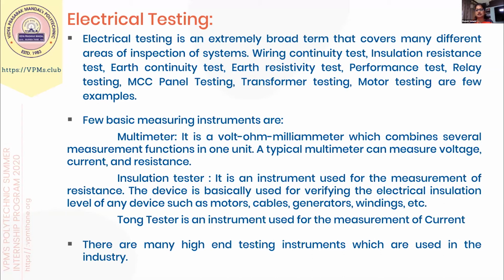Insulation tester is an instrument used for the measurement of resistance. The device is basically used for verifying the electrical insulation level for any device, such as motors, generators, cables, windings.